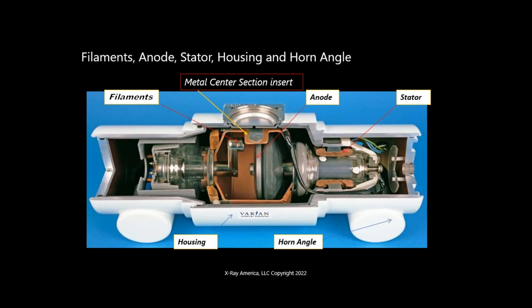So this is a bigger one. The last one was just called a 300 KHU tube. KHU refers to the heat storage in the anode. This one is, let's call it, a million or a million point five KHU. The reason is it's got a much beefier anode, it's got graphite backing. This one is what we call a metal center section. It's a different construction.